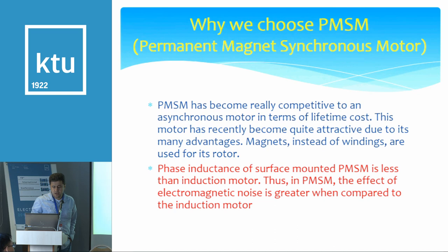But there is a disadvantage of these motors. Phase inductance of a surface mounted permanent magnet synchronous motor is less than that of an induction motor, so the effect of electromagnetic noise is greater when compared to an induction motor.